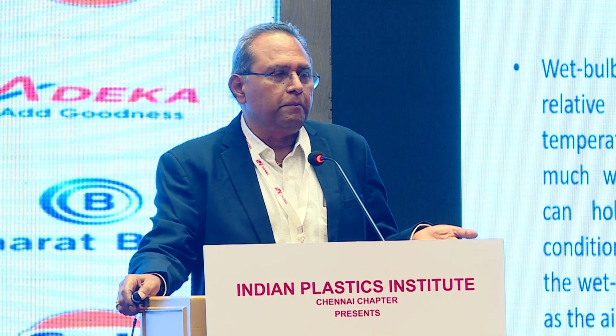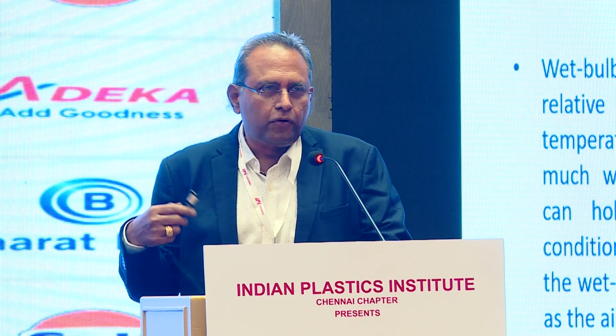So basically the concept of chilling comes in with respect to our wet bulb temperature, not the dry bulb, not the ambient. So based on the wet bulb, whatever temperature is required, will decide what kind of cooling we need for the application. So normally when applications are there which is beyond the wet bulb, that is suppose our wet bulb in Chennai is 28, you need 32, 33 degrees, then conventional cooling tower should be okay. But if you are able to accept water temperatures, cooling water temperatures above the ambient, that means let us say our maximum ambient Chennai is 40, there are a lot of applications where you can manage with 44, 45 degree cooling water temperature. In those cases, you can directly use a dry cooler. And if the process application like a mold, you need lower temperature than the wet bulb, then you have to go only for the refrigeration chiller.